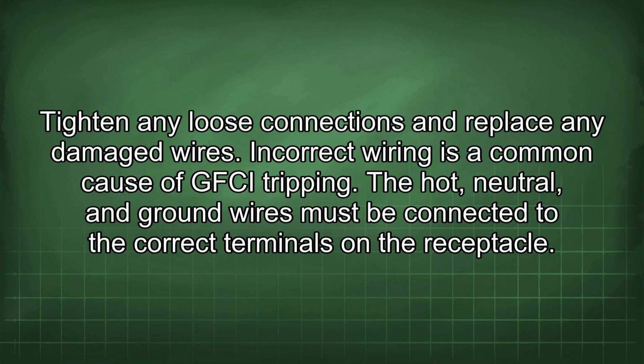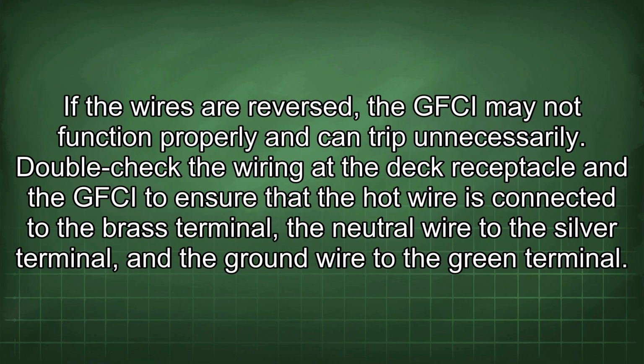Incorrect wiring is a common cause of GFCI tripping. The hot, neutral, and ground wires must be connected to the correct terminals on the receptacle. If the wires are reversed, the GFCI may not function properly and can trip unnecessarily. Double-check the wiring at the deck receptacle and the GFCI to ensure that the hot wire is connected to the brass terminal, the neutral wire to the silver terminal, and the ground wire to the green terminal.